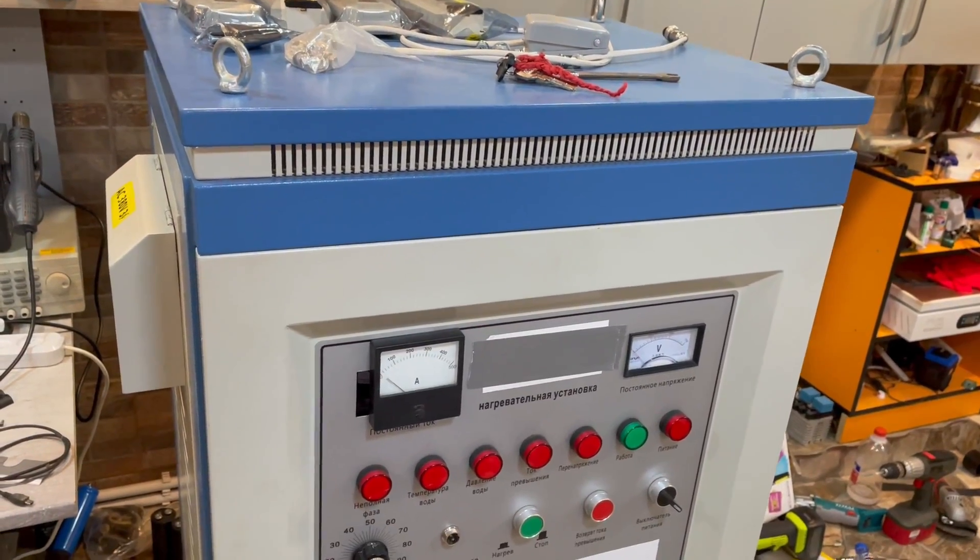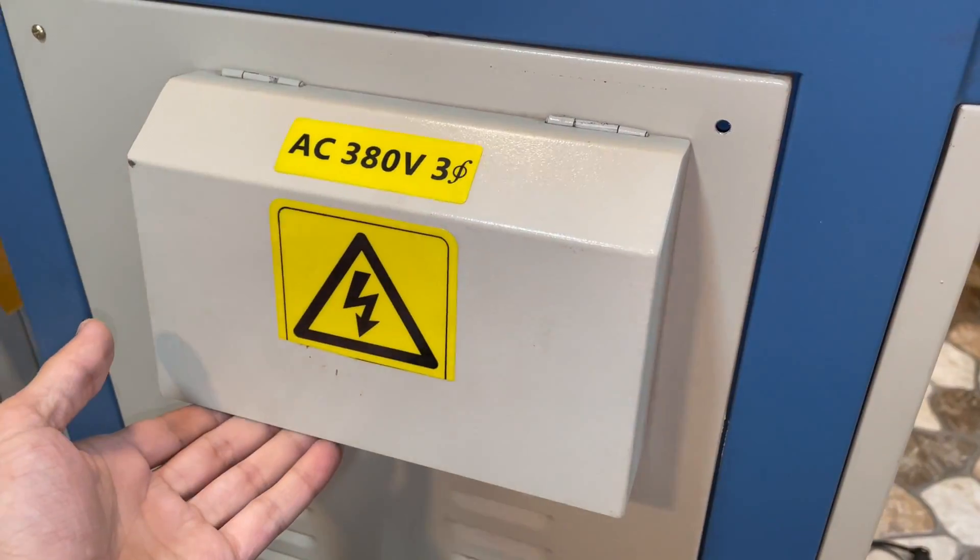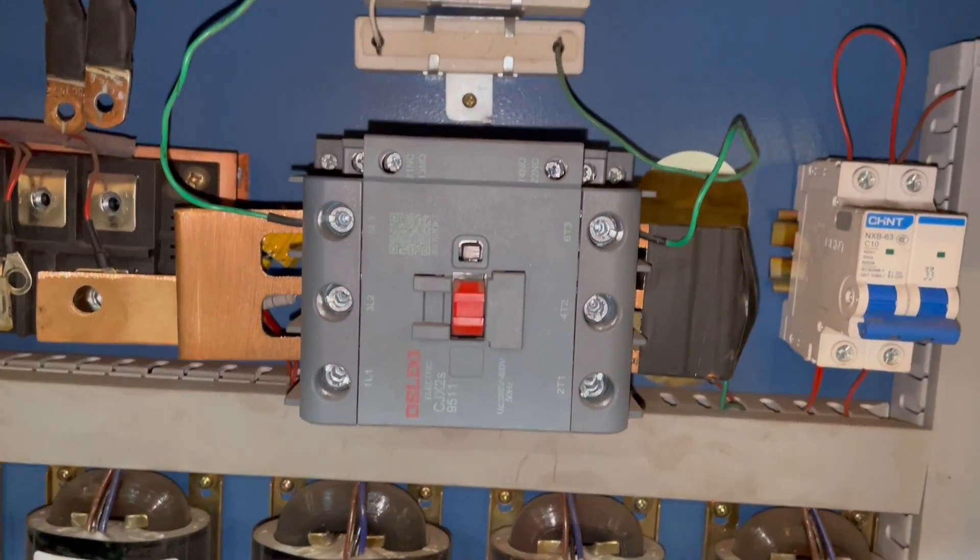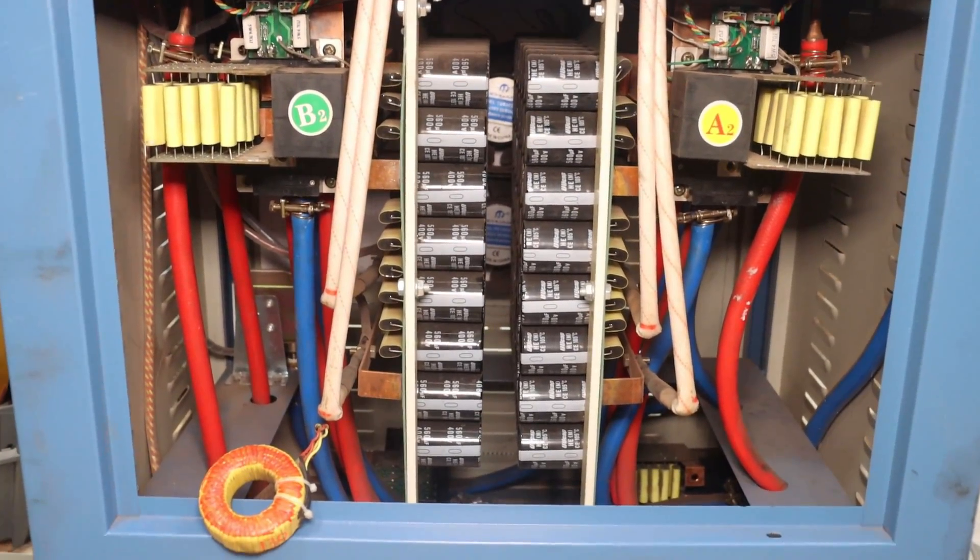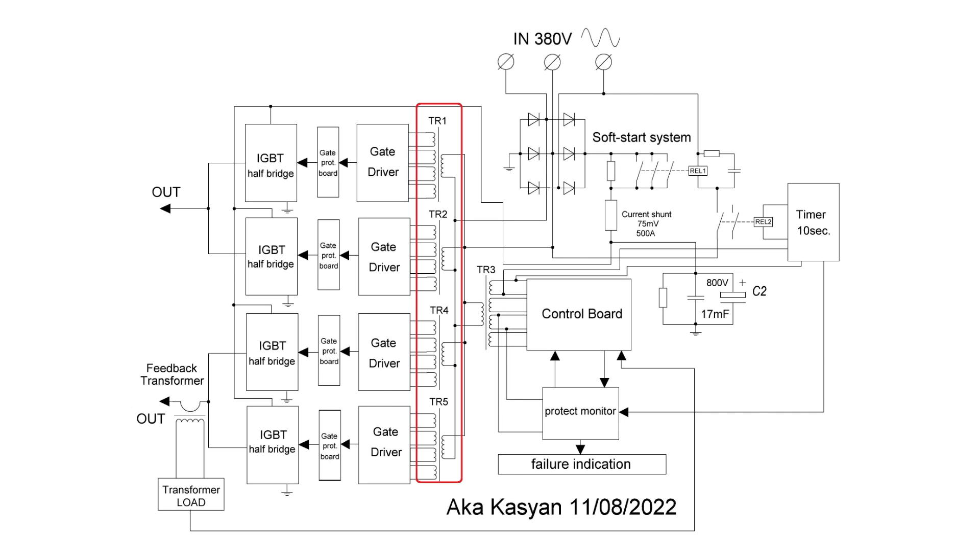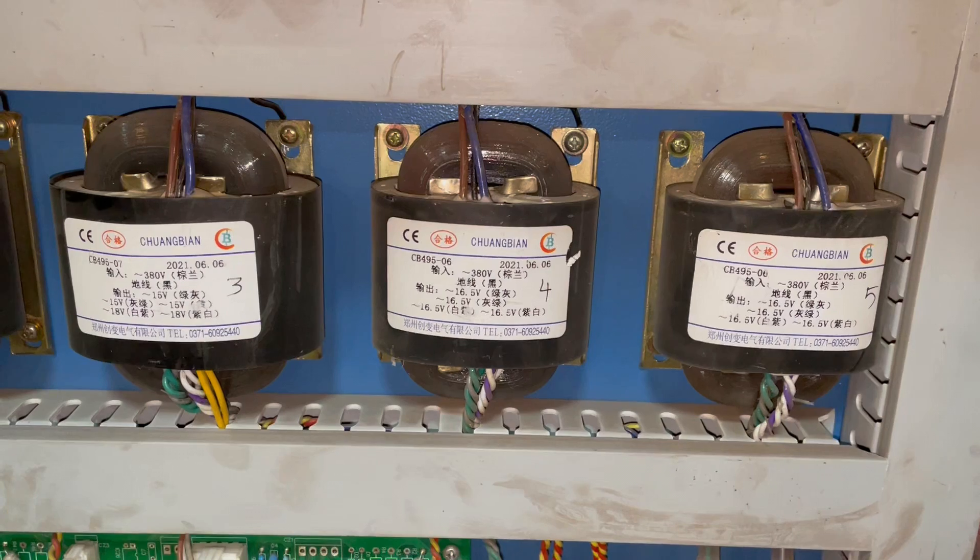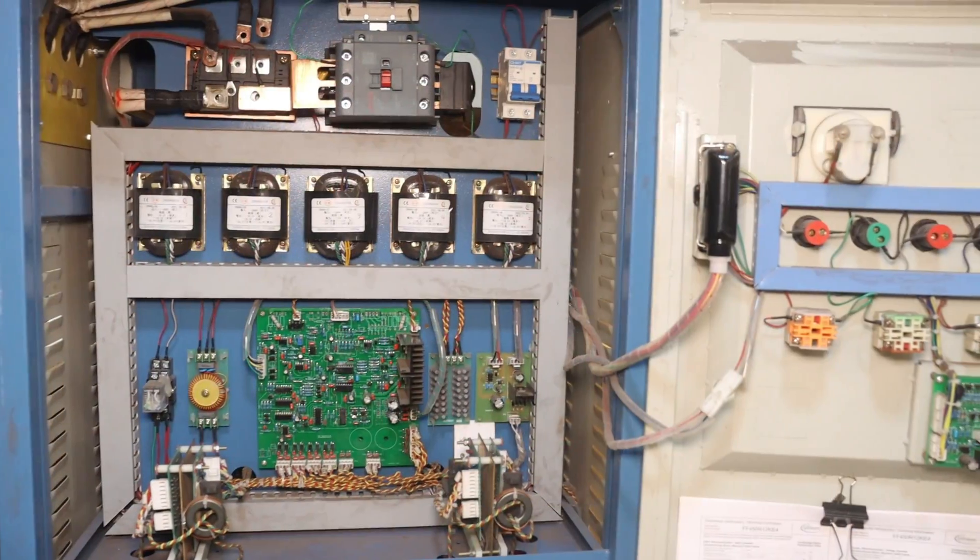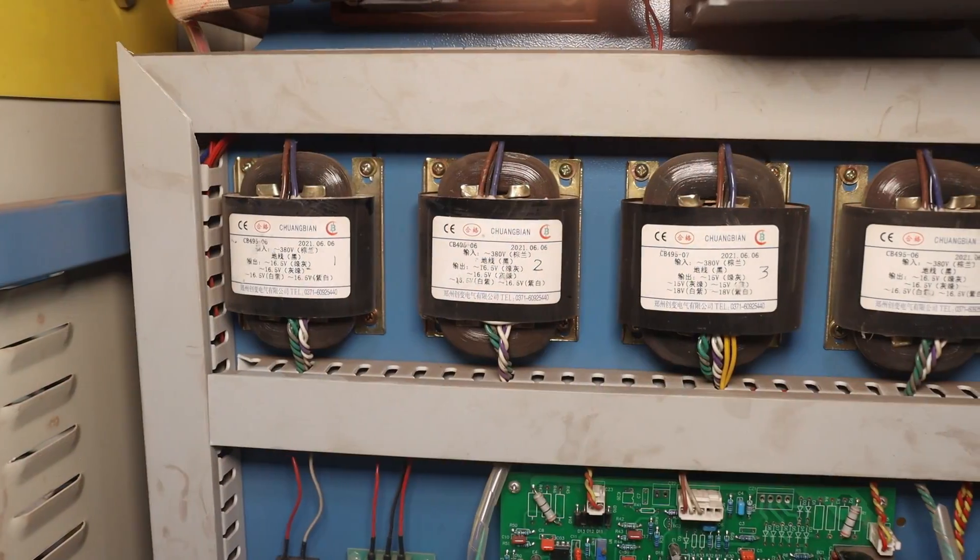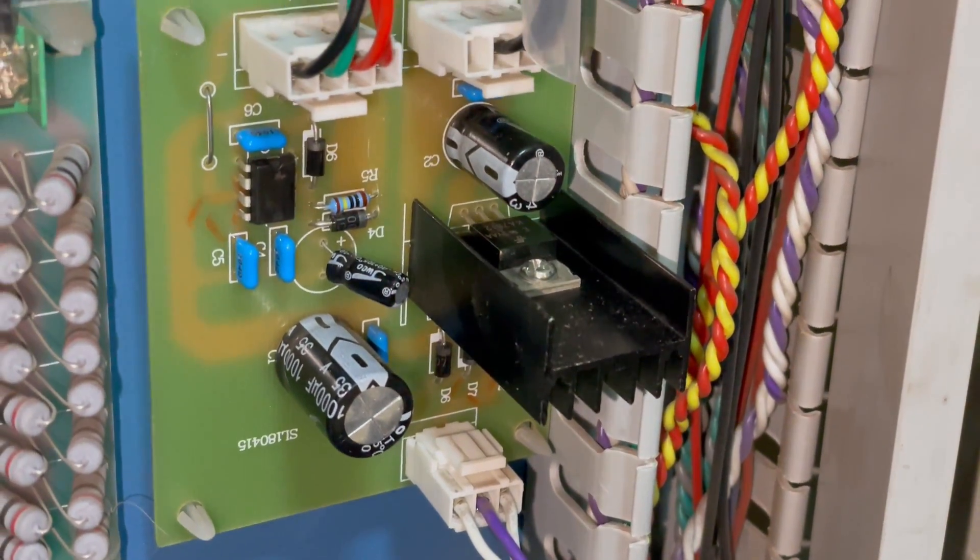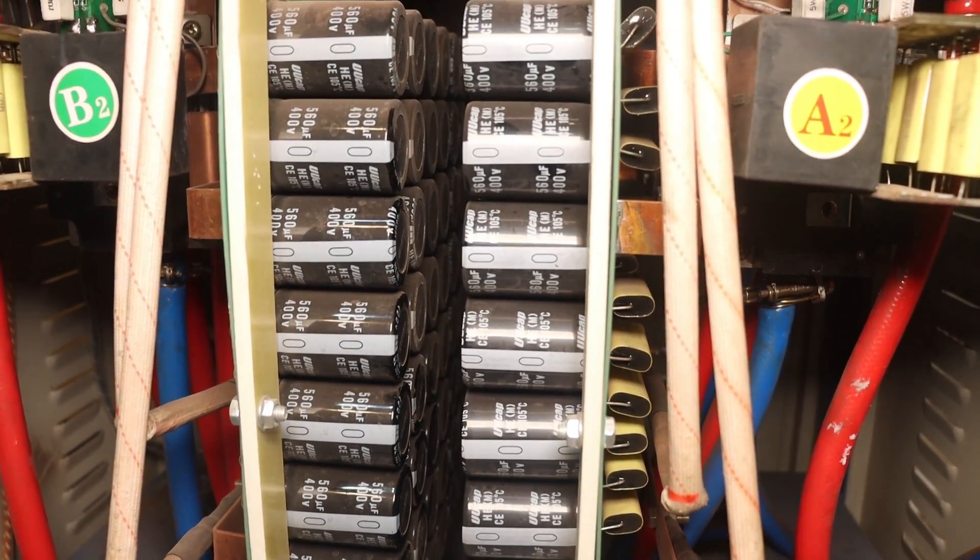In a nutshell, I will explain what nodes it consists of and how it works in general. The 3-phase 380V voltage is rectified and through current limiting resistors charges a huge bank of capacitors. In parallel, from the input power goes directly to low-powered transformers. There are five of them. Four of them are the same and feed the drivers of the power control modules. The middle transformer forms several power supply lines for control systems. In general, immediately after switching on, the power from the transformers is distributed to all nodes. It also goes to this small board. All this time capacitors are charged with a limited current.